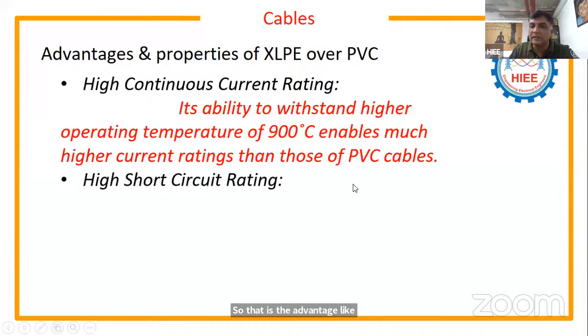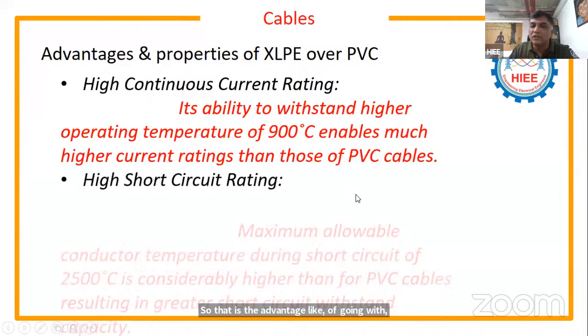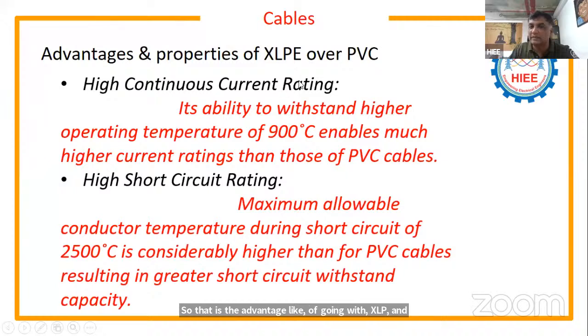And high short circuit current. When you're going with XLPE insulation, the cable short circuit current will be higher. The maximum allowable conductor temperature during short circuit, almost 250 degrees centigrade, is considerably higher than for PVC cables. So that is one more advantage with the XLPE.